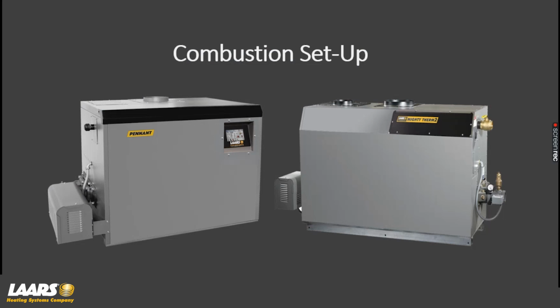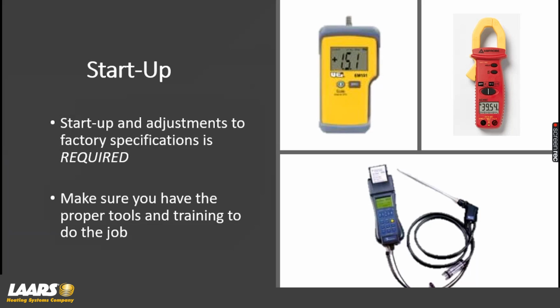Next, we're going to talk about combustion setup for these products. Now, combustion setup or startup, follow the factory's specifications. I don't care who the manufacturer is, you really need to read that information. Some manufacturers might be looking at O2. Most manufacturers look for CO2 with an analyzer. So again, make sure you're following their procedure.